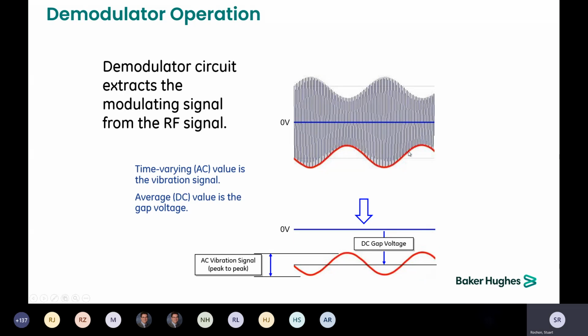So once we extract that demodulated waveform, we generally measure peak to peak for your peak to peak vibration. So measuring from the lowest point to the highest point, we get your peak to peak. We can also do peak, RMS, and other values can be calculated from that waveform. The DC gap voltage is the average value of that waveform. So the DC gap gives us basically the distance the shaft is from the probe tip, and the AC component is the vibration movement.